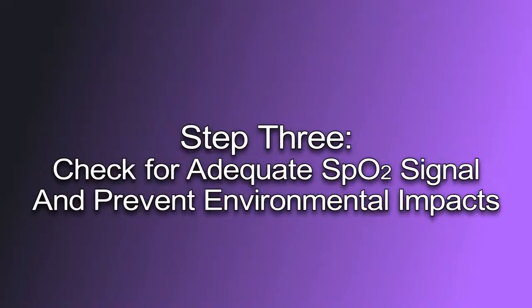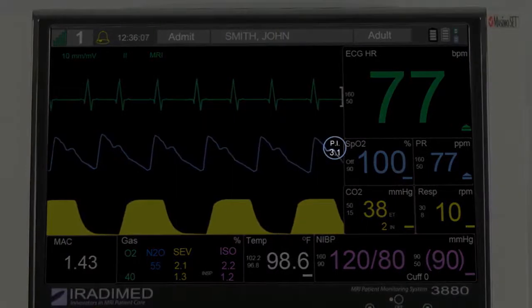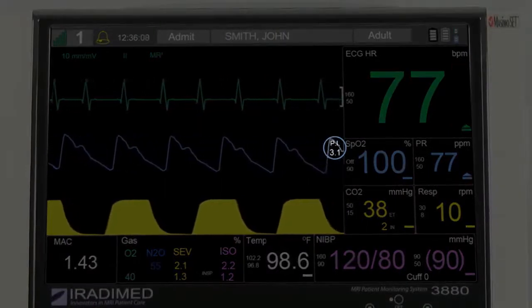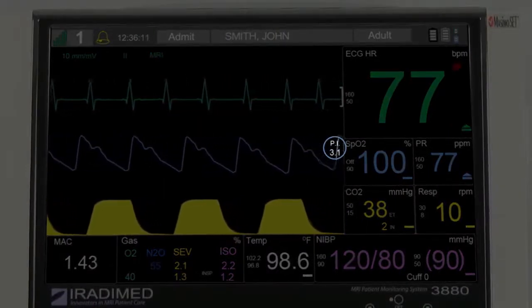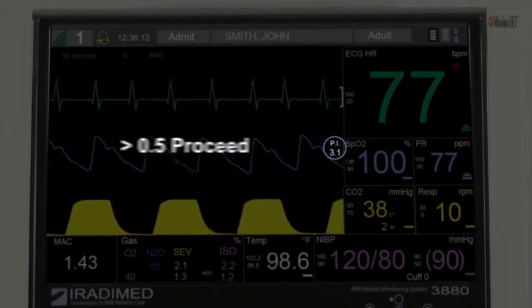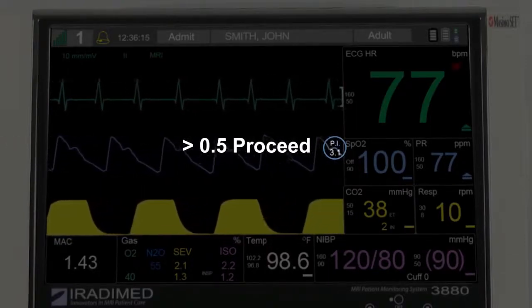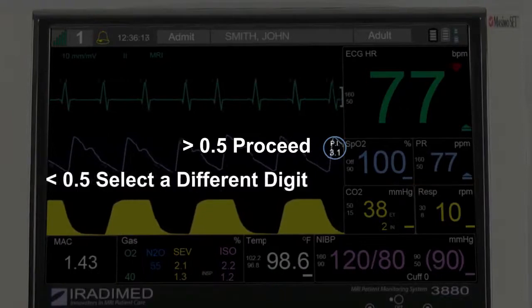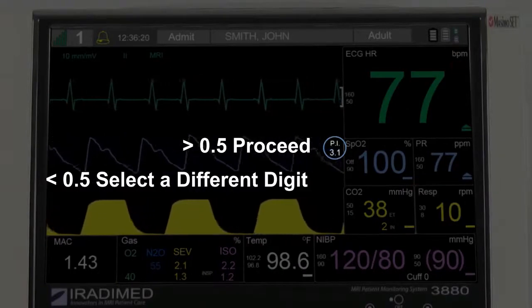Step 3. Check for adequate SPO2 signal and prevent environmental impacts. Check the perfusion indicator to ensure ample signal is being detected by reviewing the PI number on the SPO2 waveform. If the signal is greater than 0.5, then proceed. If the perfusion indicator is less than 0.5, then select a different digit and proceed to step 2.